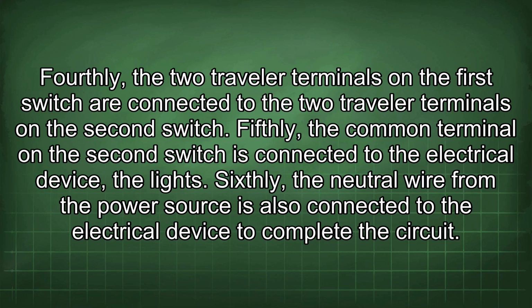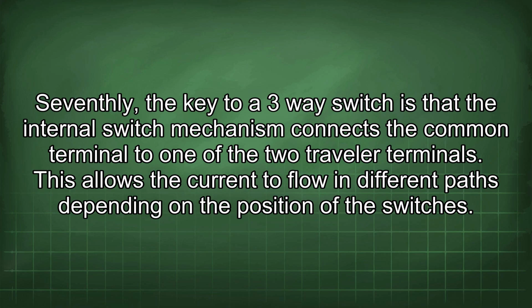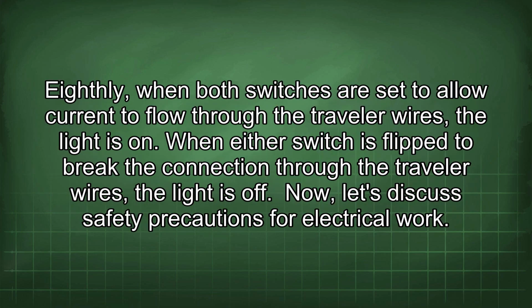Fifthly, the common terminal on the second switch is connected to the electrical device, the lights. Sixthly, the neutral wire from the power source is also connected to the electrical device to complete the circuit. Seventhly, the key to a three-way switch is that the internal switch mechanism connects the common terminal to one of the two traveler terminals. This allows the current to flow in different paths depending on the position of the switches. Eighthly, when both switches are set to allow current to flow through the traveler wires, the light is on. When either switch is flipped to break the connection through the traveler wires, the light is off. Now, let's discuss safety precautions for electrical work.